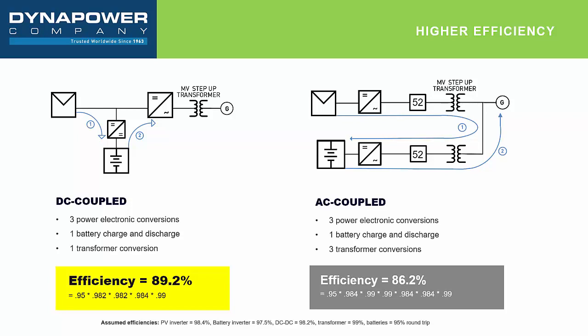Then when we discharge to the grid, we go out through the storage inverter and then up and out through the medium voltage transformer to get to the grid. So the net effect, when you look at DC coupling, is you have 3 power electronic conversions and 1 transformer conversion. Whereas with AC coupling, you have 3 power electronic conversions and 3 transformer conversions.